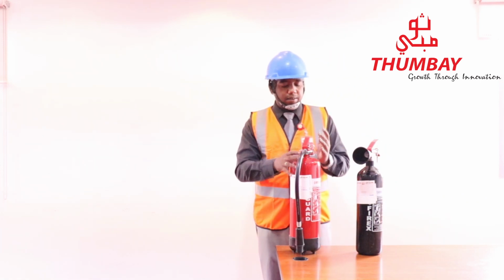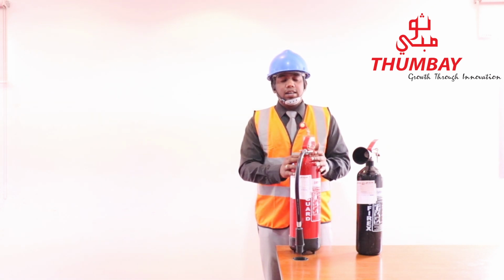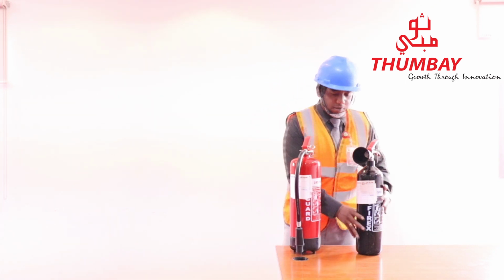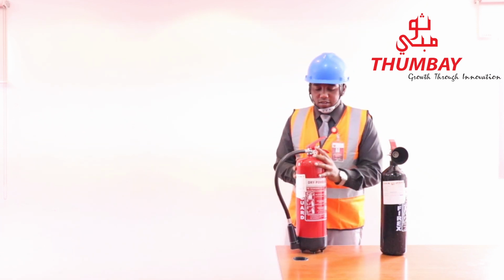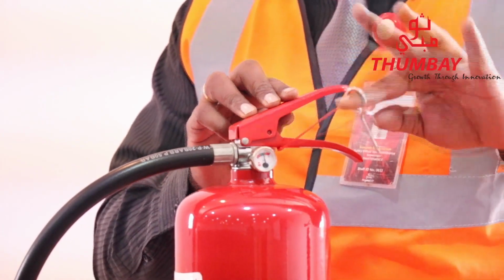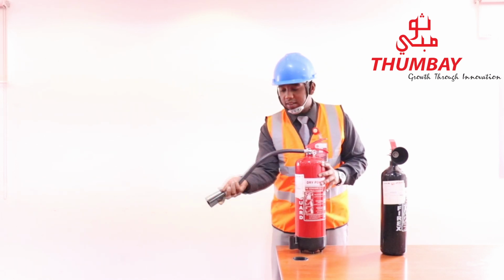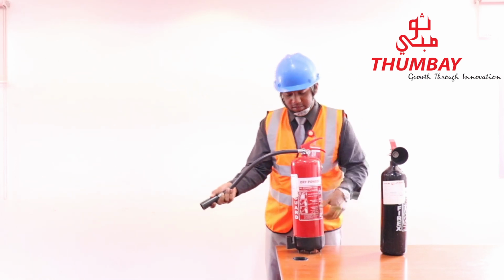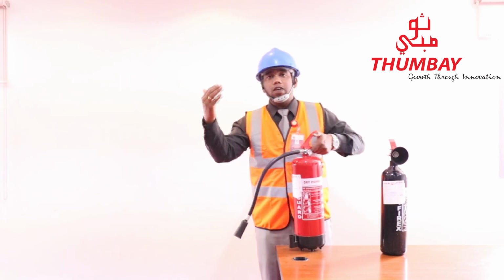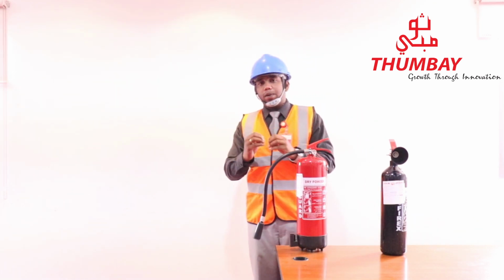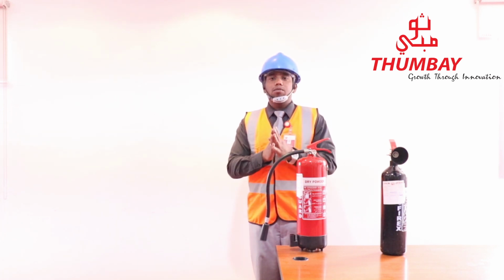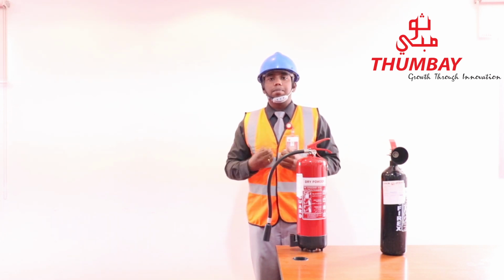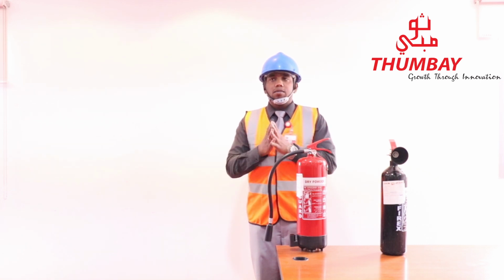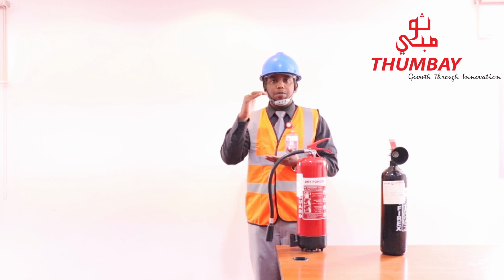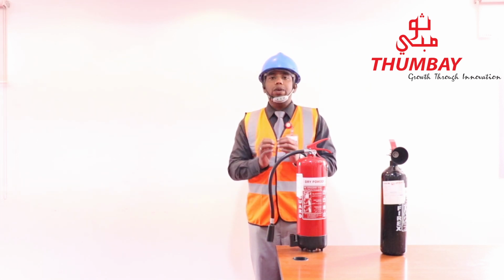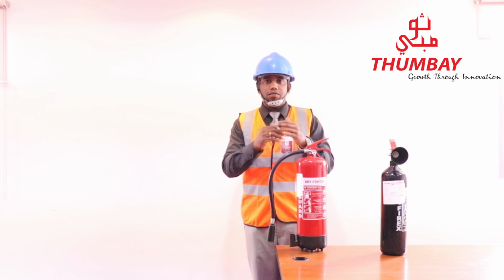Now we're going to see the PASS method, which is the universal method used by extinguisher users. I'm going to demonstrate very slowly. See, this is a safety pin right here. You pull the pin and hold the hose. That means P. Aim at the base, not above the flames or through the flames, because we need to separate the source from the flames. Whatever the source may be, wood, or fuel, or gas, it lies down there, and the flames are above. So we aim at the base to separate the flames from the source.